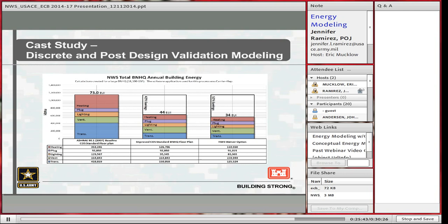Okay, so the previous question about plug loads, part of this is a standard requirement by Appendix G and ASHRAE 90.1. So there's a preset amount of plug loads, and that's why you don't necessarily see it reducing, because it's something that has to be considered standard. And if you're going to change it, I believe ASHRAE requires some exemplary calculations as part of it. I hope that answers the person's question. It all goes back to ASHRAE 90.1.